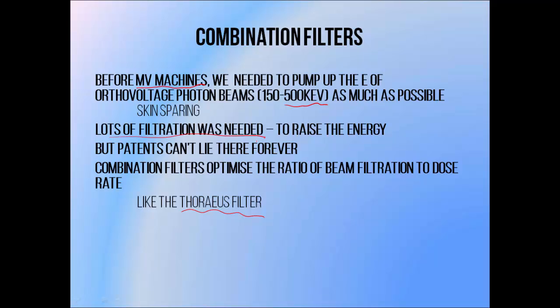But beam filtration increases the average beam energy at the expense of the dose rate, because you're cutting more photons out of your beam, which means fewer will reach the patient and deposit dose. So extreme beam filtration can result in treatment times that are impractically long. One way to get around this is to use combination filters, which allow us to increase our beam energy with a minimal loss in dose rate.